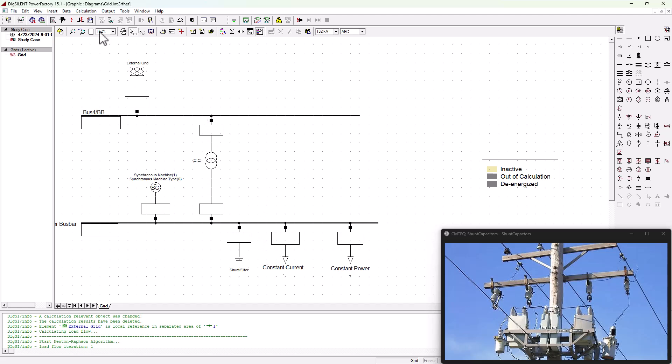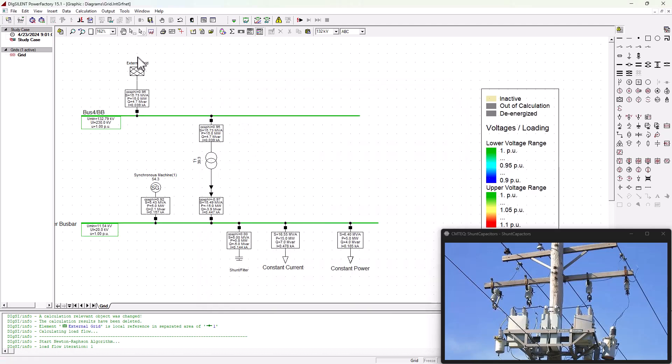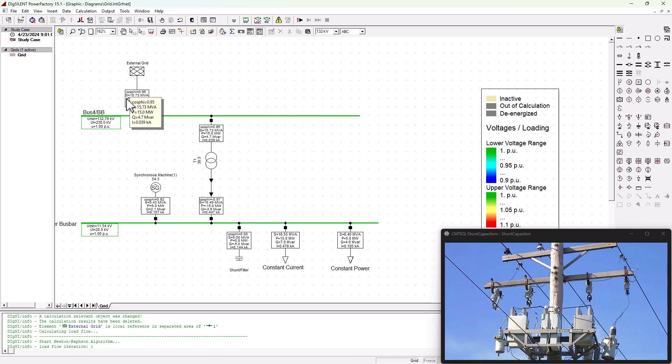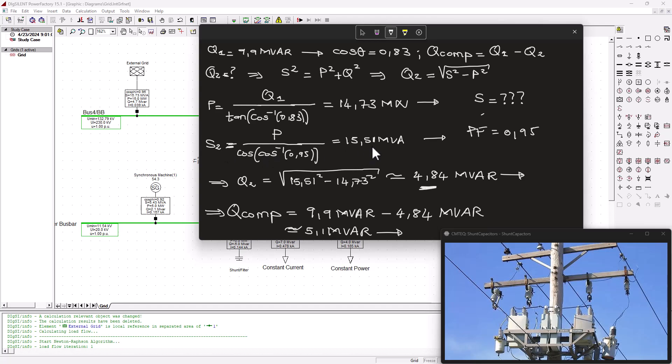Great. Now all we have to do here is to run the load flow analysis so we can confirm that the power factor has actually been improved from what it was to the new value. And as you can see here, the power factor is 0.95, exactly the way we calculated it. And the apparent power is 15.7, power is 15, Q is 4.7. And as we can see here, everything actually checked out, right? Q2, the compensation, is 4.8, and over here is about 4.7—calculation and measurement discrepancies. P 14.7, and S 15.51 MVA—we've got 15.7 and 15, so it basically checked out as you can see.